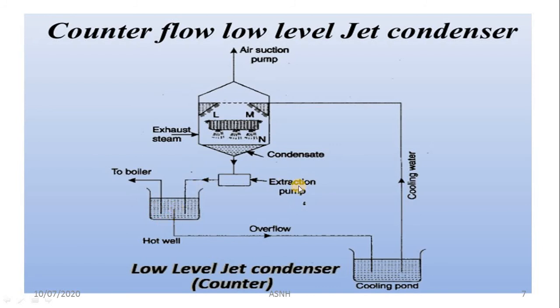So it is called a counterflow jet condenser, or that particular barometric type jet condenser. So counterflow and barometric are the same as far as working is concerned. The only main difference is the absence of a condensate extraction pump in the barometric type condenser. Another name for the barometric condenser is high level jet condenser, because in the absence of a condensate extraction pump, the condensate directly enters the hot well because of gravity force.